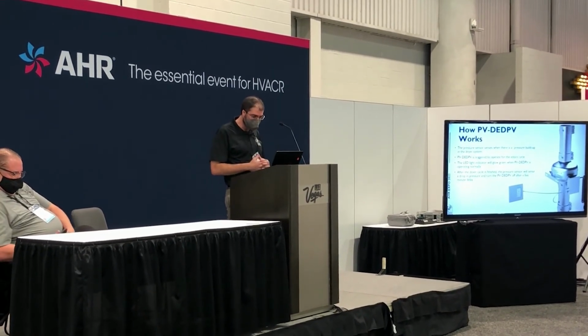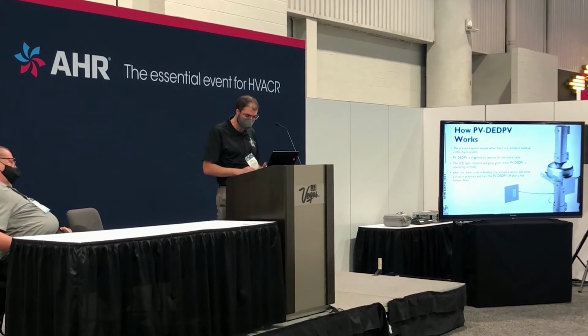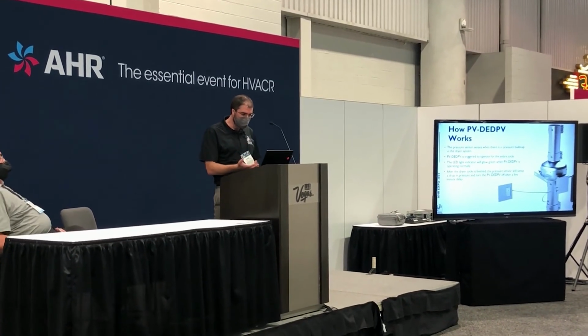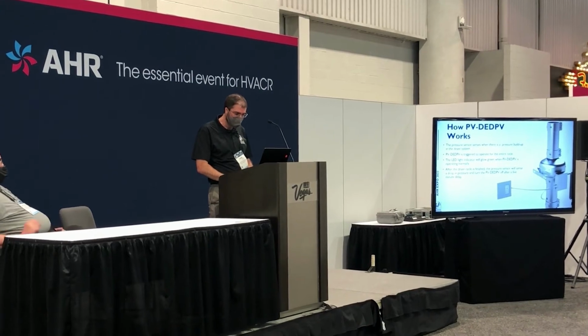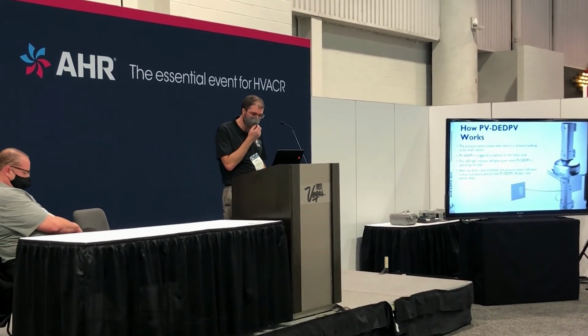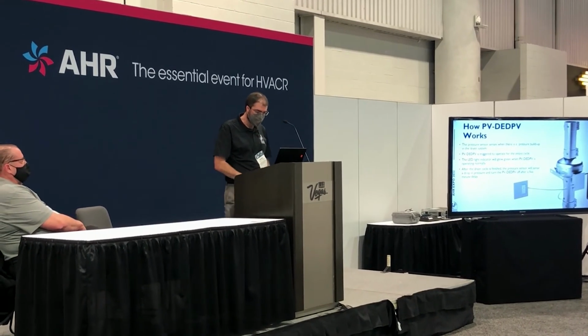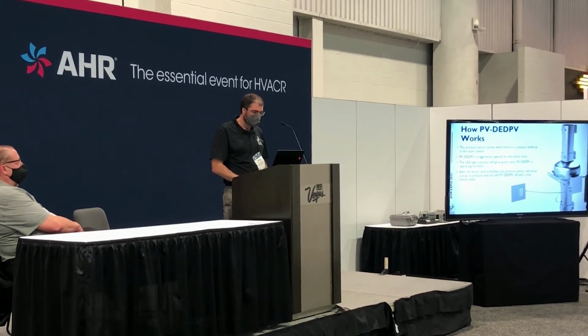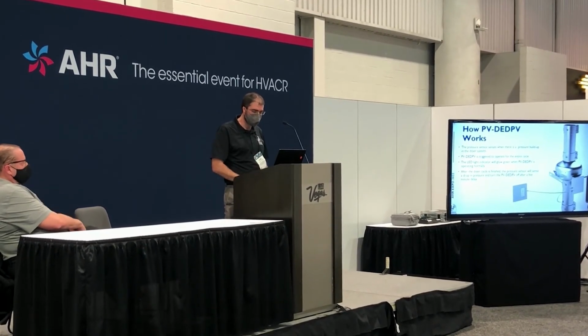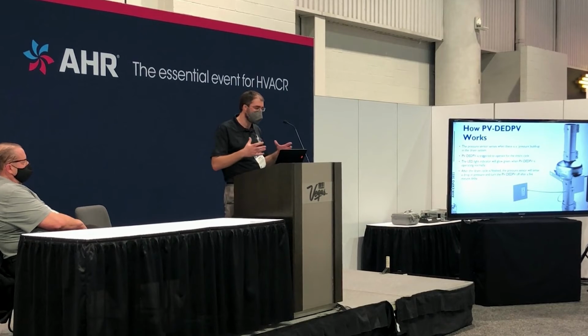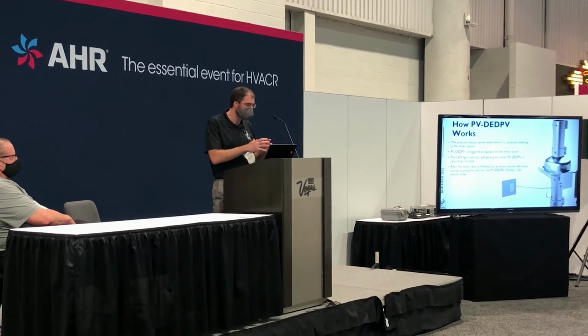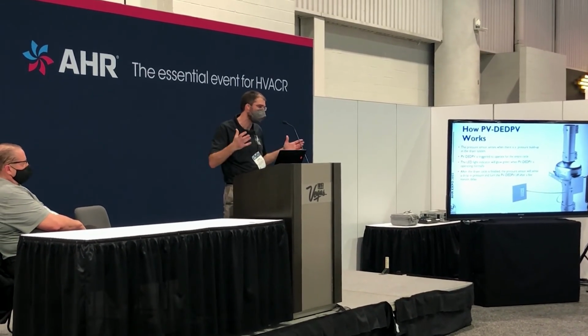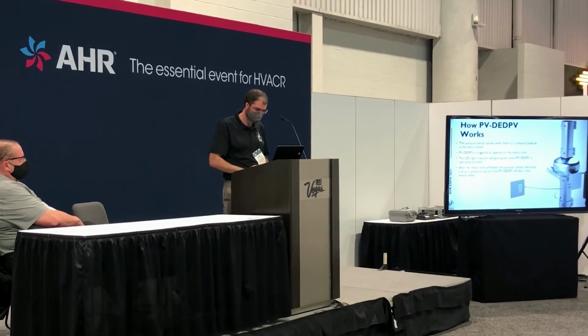And then we have to talk about air movement. That matters greatly in the dryer exhaust system. So the PV-DEDPV is designed to maintain a minimum air velocity of 1,200 feet per minute and a maximum of 2,200 feet per minute, and to maintain that velocity range up to a maximum of 120 lineal feet of ductwork.